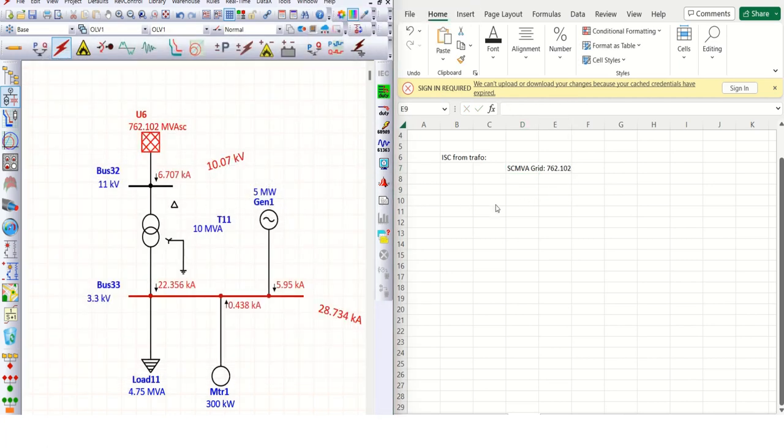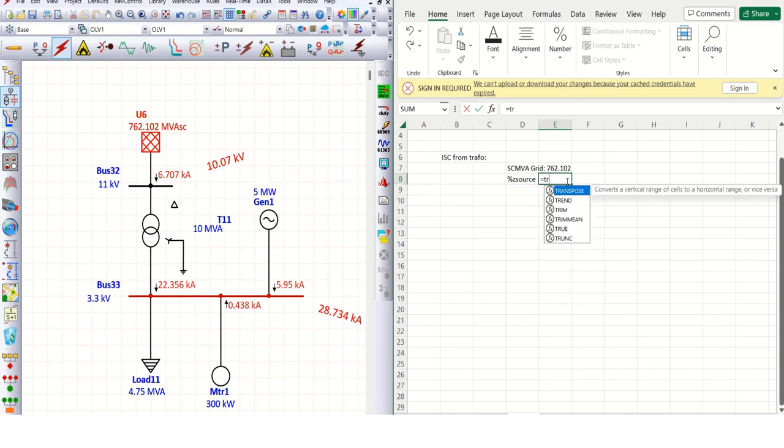Then, if you want to find out the percentage of source impedance, this is equal to your trafo MVA divided by short circuit MVA, which is specified by the grid authority.